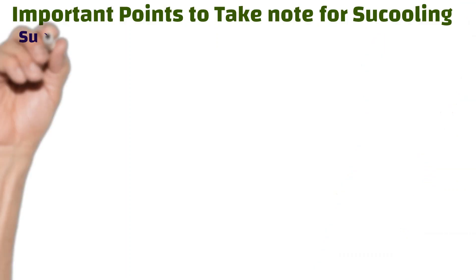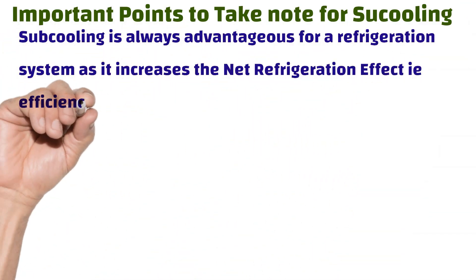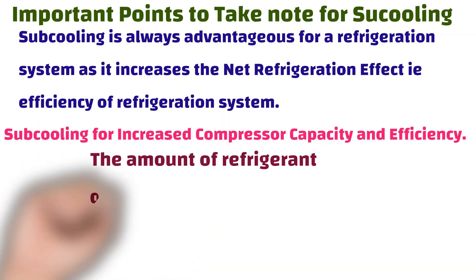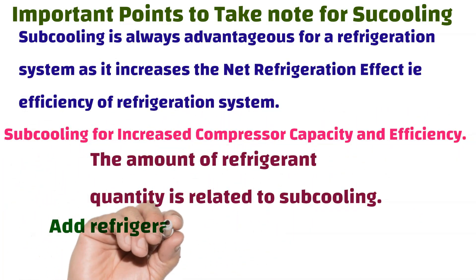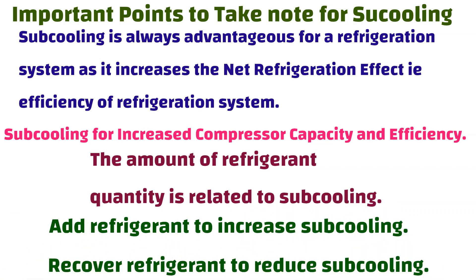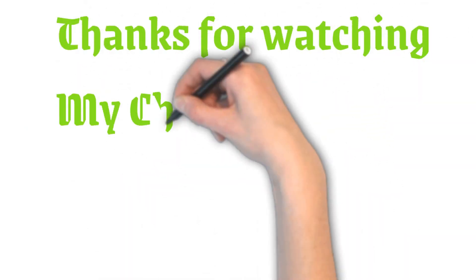Important points to note: sub-cooling is always advantageous for a refrigeration system as it increases the net refrigeration effect, which is the efficiency of the refrigeration system. Sub-cooling also increases compressor capacity and efficiency. The amount of refrigerant is related to sub-cooling — add refrigerant to increase sub-cooling, and recover refrigerant to reduce sub-cooling. Thank you all, please like, comment, and share my channel with your friends.